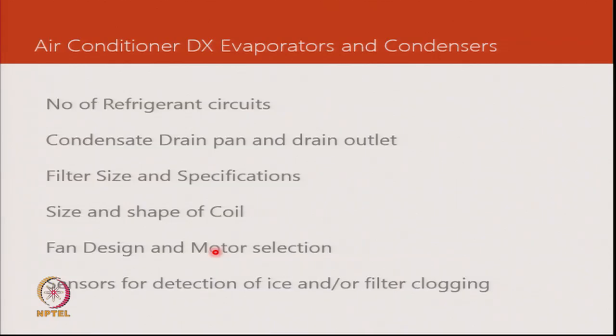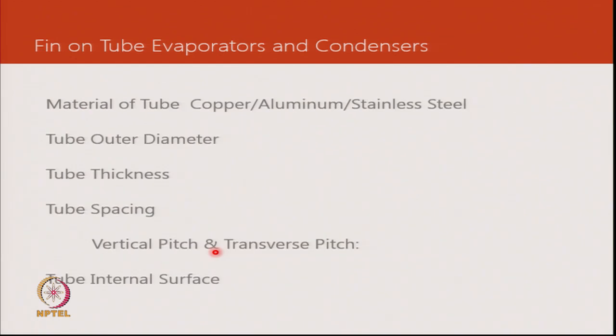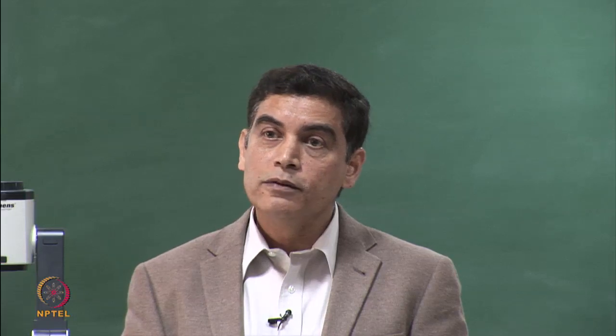The variables we can play with for a fin-on-tube heat exchanger include: material of the fin, fin thickness, fin spacing, fin type, and fin coating. The tube material could be copper, aluminium, or in special cases stainless steel — primarily for corrosion resistance in marine environments or defence applications where robustness is preferred over low cost. We also need to define the vertical and transverse pitch.